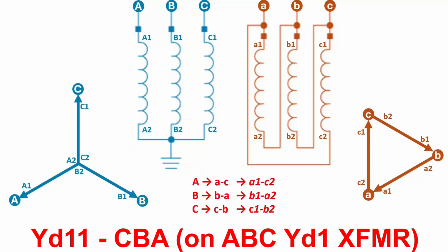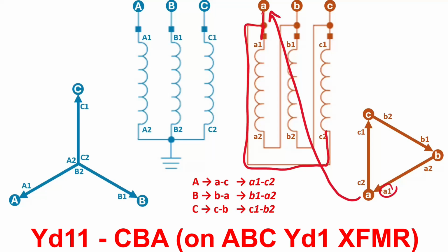It's really easy, right? However, what does change is our A and C phasors change position. And since they change position like this, C is now pointing up, which is right here. And A is now pointing down and to the left, which is right here. All right. So what's our terminal connection? Well, our A tap is right here, and that's going to be right there. And it connects obviously to A1, and the other one connects to C2. Okay, that works out exactly.